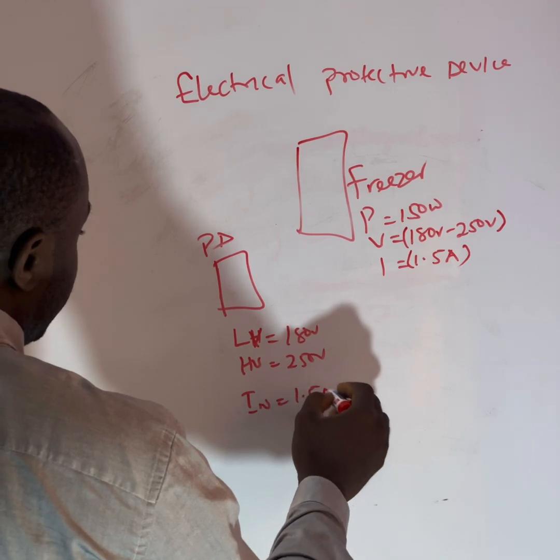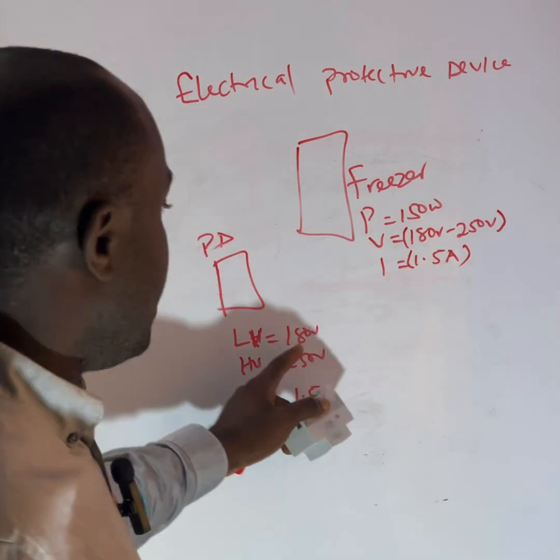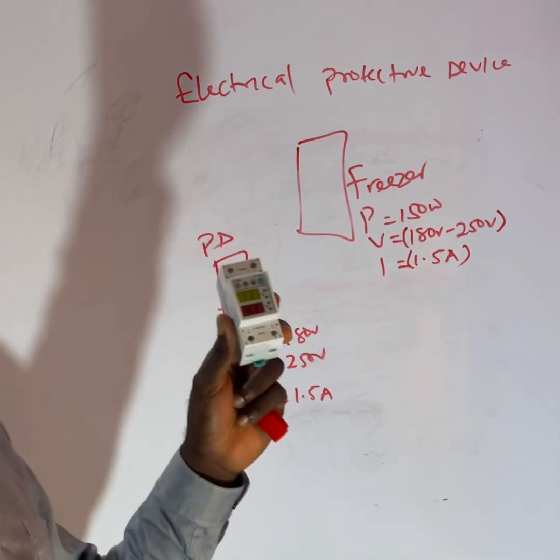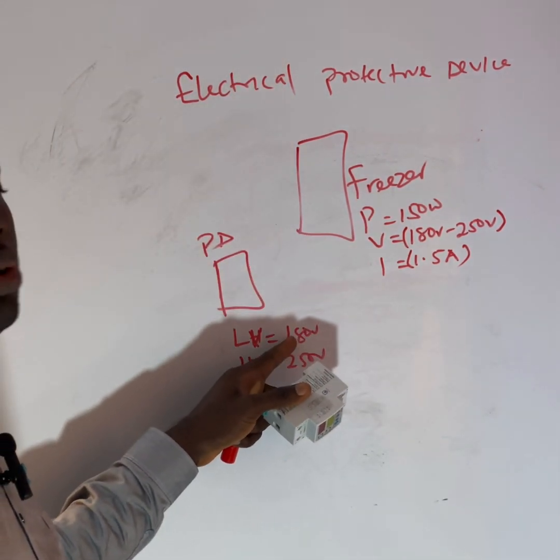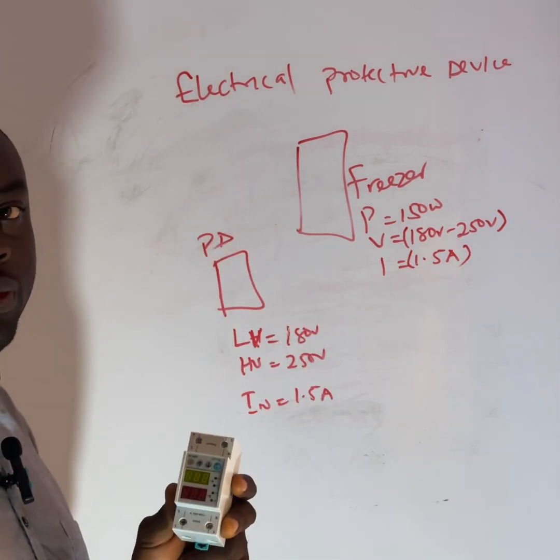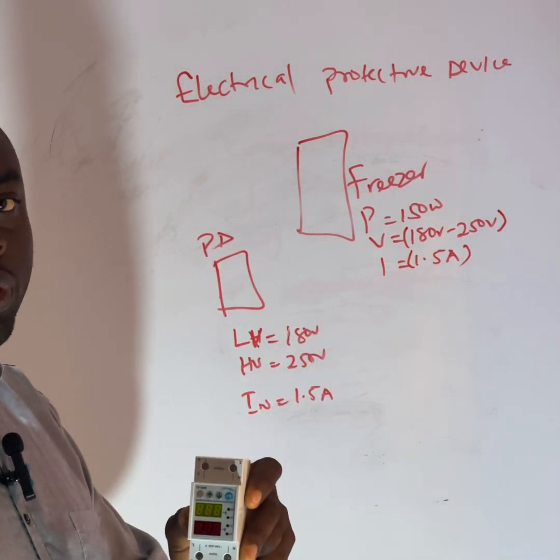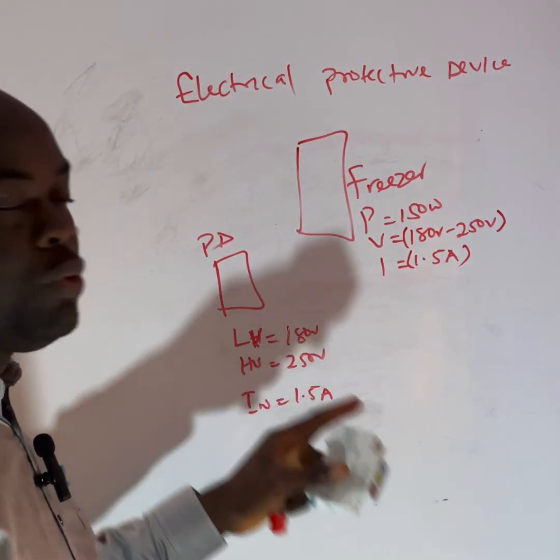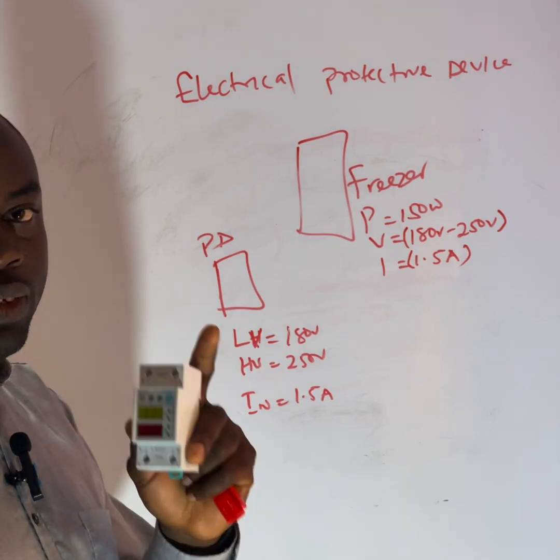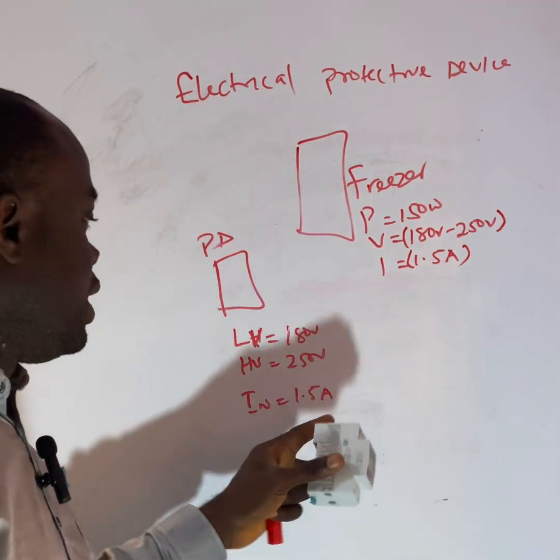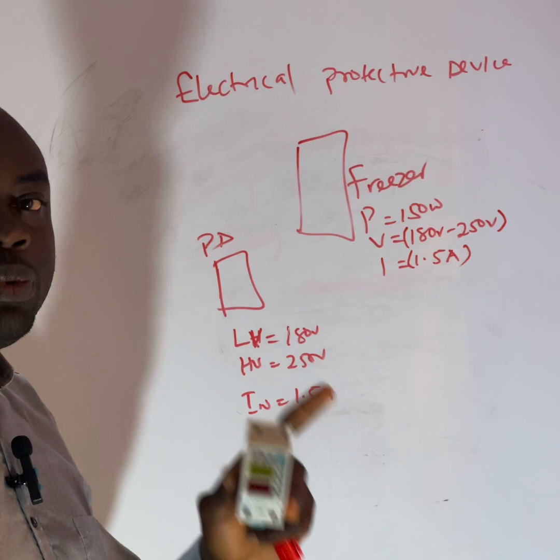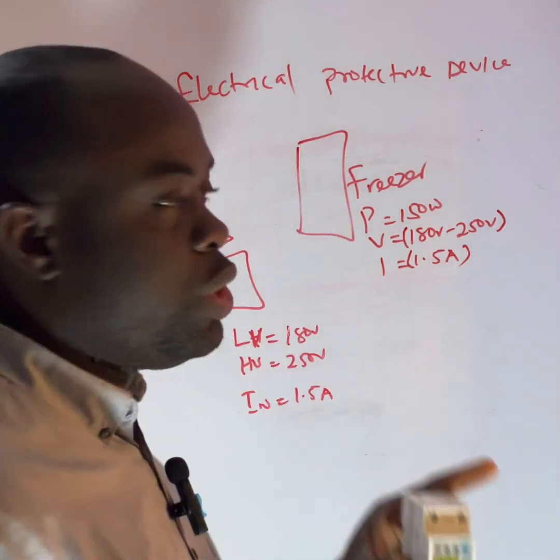And the current also, you are going to set it to 1.5 amps. It means that any voltage coming into this device in my hands, any voltage below 180 volts, shut it off, meaning this device will trip off, it will cut off, and your freezer will go off. Any voltage above 250 volts, cut it off, this device will trip off and your freezer will go off. Any current above 1.5 amps, cut it off, this device will go off and the freezer will go off.